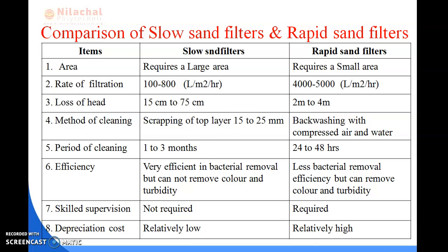Next is the method of cleaning the filters. In the slow sand filter, the top layer of 15 to 25 millimeters is scraped and removed, and in the rapid sand filter, backwashing is done with compressed air and water. Next is the period of cleaning, how many months or hours are required. The slow sand filter requires 1 to 3 months, and the rapid sand filter requires 24 to 48 hours for cleaning.